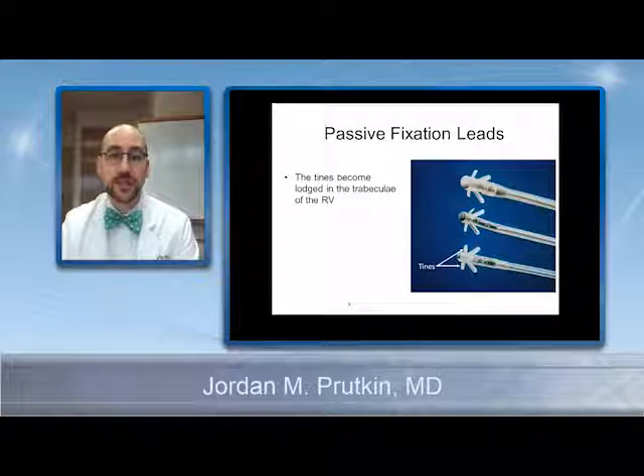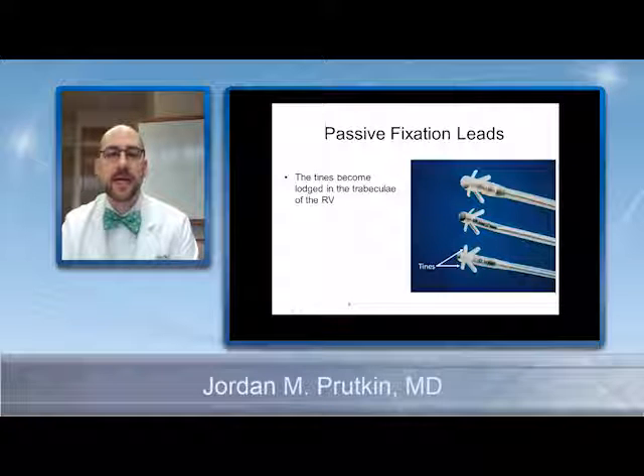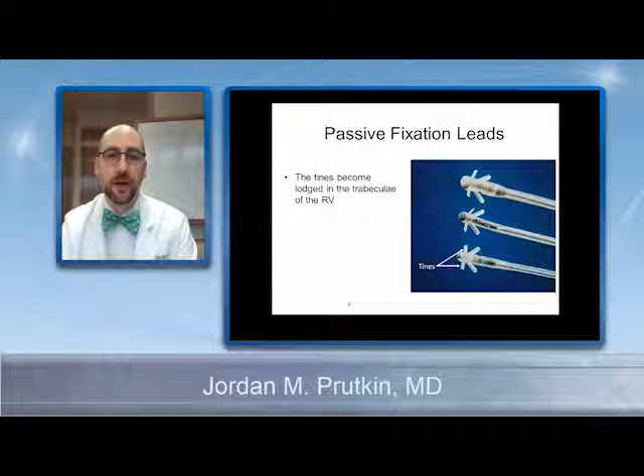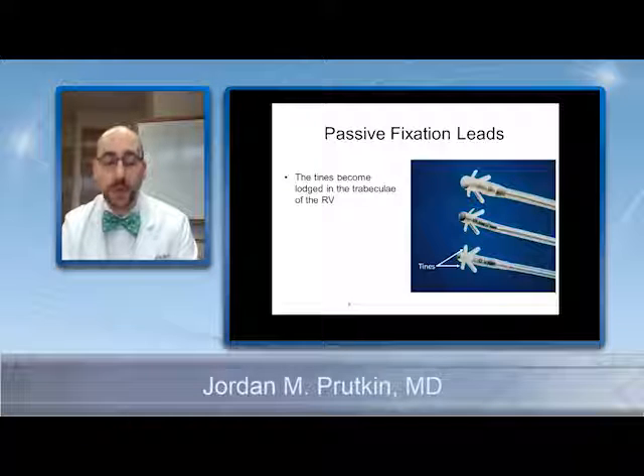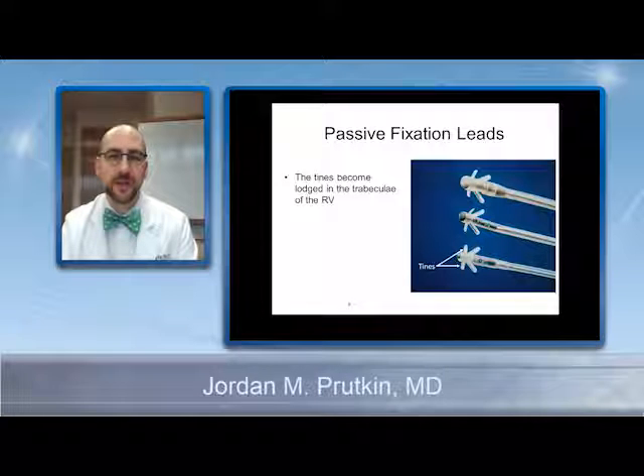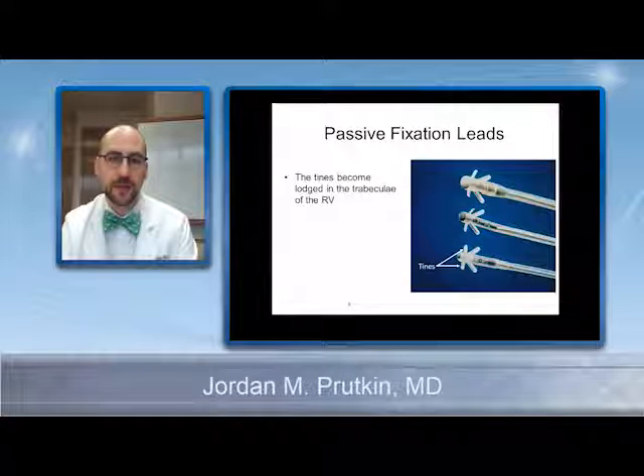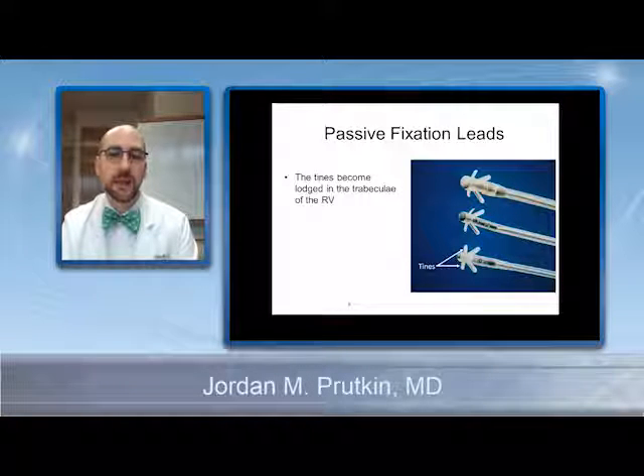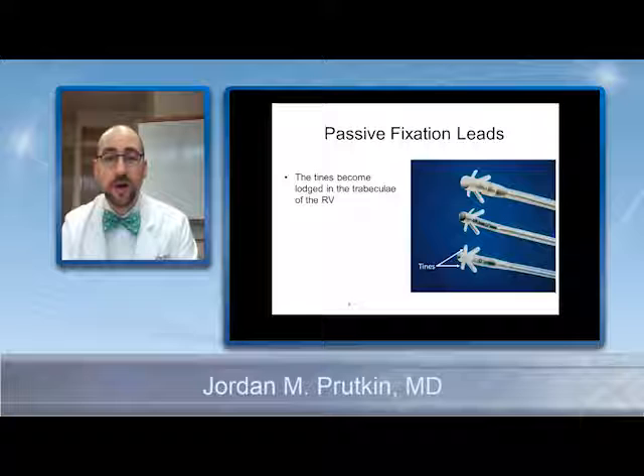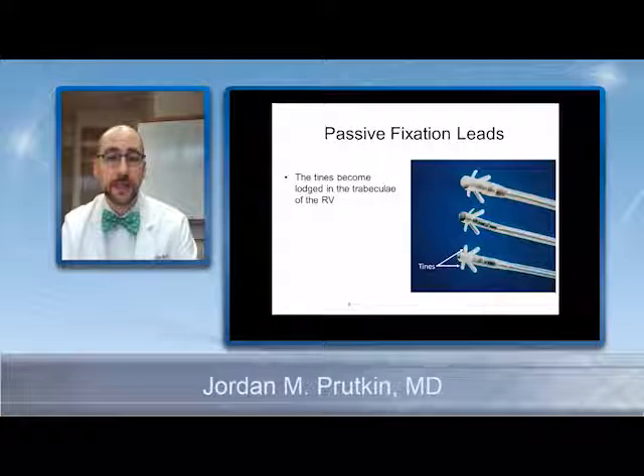Passive fixation leads have tines on the end of them. You can see pictures of different types of the leads here with these tines. What happens is that those tines get lodged in the trabecula of the right ventricle, or the right atrium if you're going to put them in the atrium. It allows the lead to stay fixed in place without pulling backwards because those tines provide an active force to prevent the lead from being pulled backwards. The benefit to a passive fixation lead is that oftentimes you'll have a little bit better threshold, so that means less energy needed for them, but the downside is that they can really only be placed in the apex.